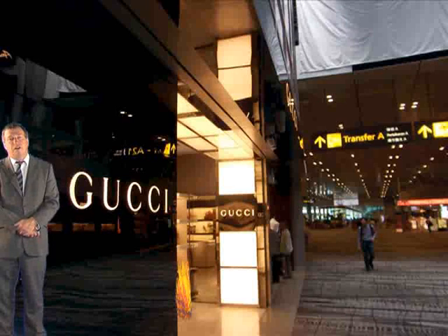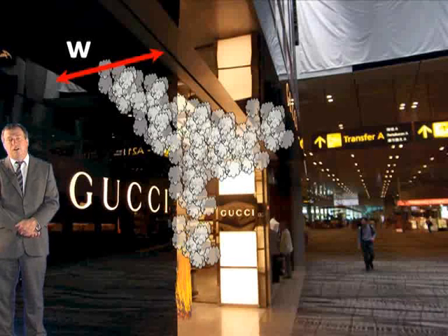If this is the case, and there are none provided, then it is assumed that the smoke will expand sideways a little as it flows towards the spill edge. The extent of sideways expansion is assumed to be equal to the distance from the opening to the spill edge, and this is known as WB.